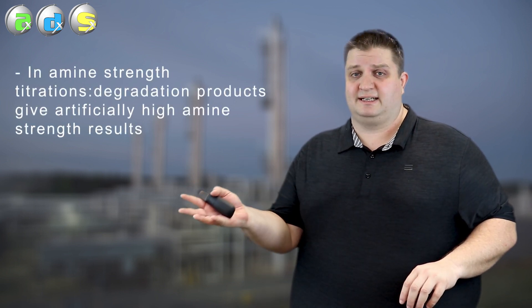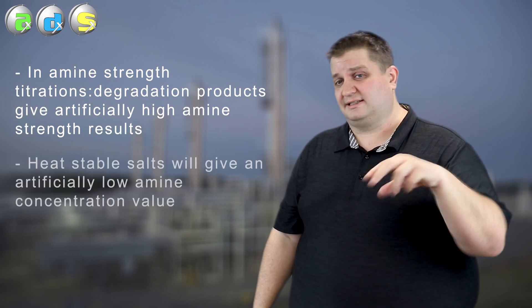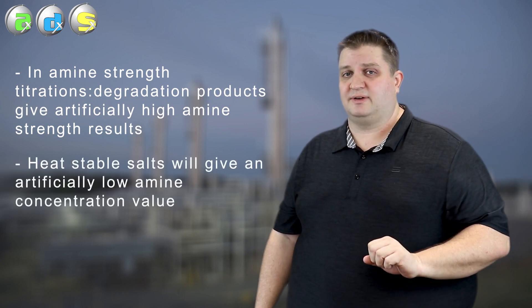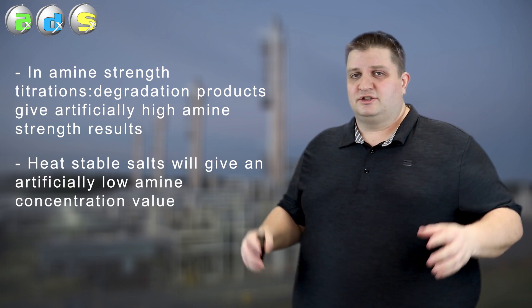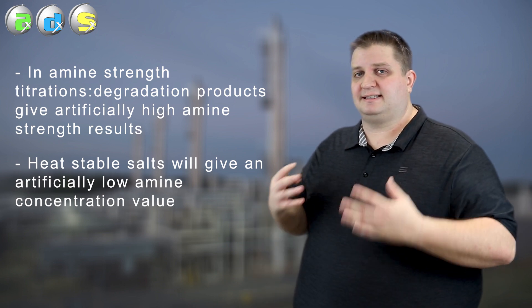What these tests don't tell you though is how the heat stable salts and degradation products are affecting those results. If you start getting too high in your degradation products you're going to see an artificially high amine strength compared to what you're actually using in the system. If your heat stable salts are too high it's going to do the reverse. It's going to drop the effective amine strength you actually have in the system. To really see the full picture you need to package that amine up and send it to an off-site lab to get a full analysis done.